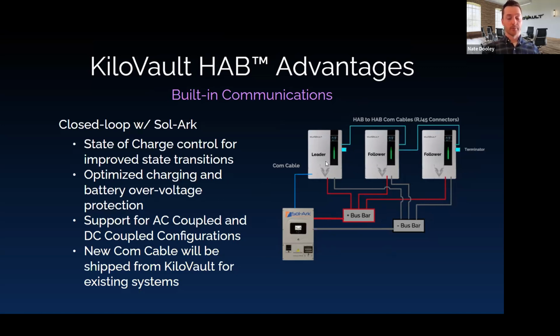This closed loop communication refers to communication between your battery bank and your inverter. The first example here is with the Sol-Ark 12K. We will support closed loop communications, and what this does is allow the BMS of the battery to communicate via Modbus directly with the inverter, so it can communicate its charge and discharge limits and its state of charge directly to the inverter.